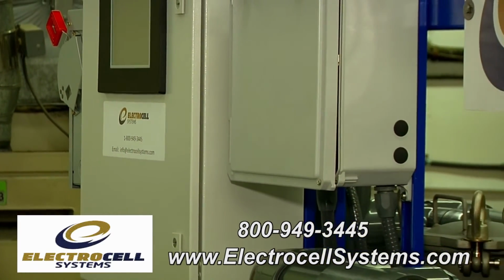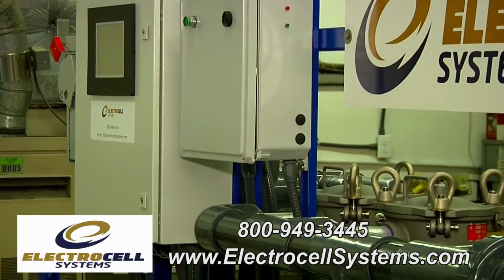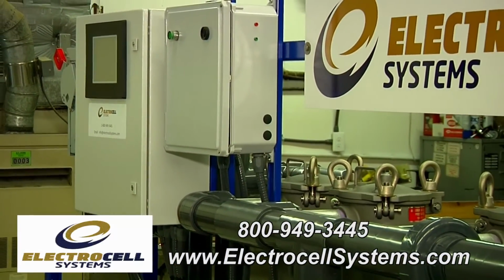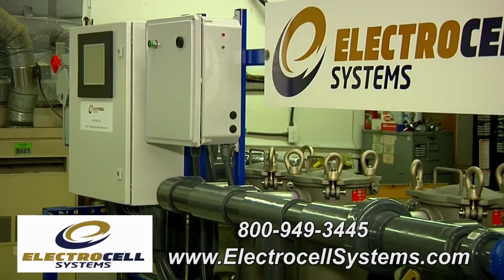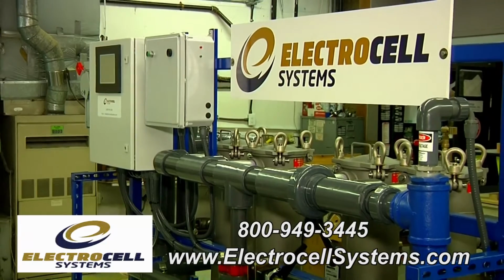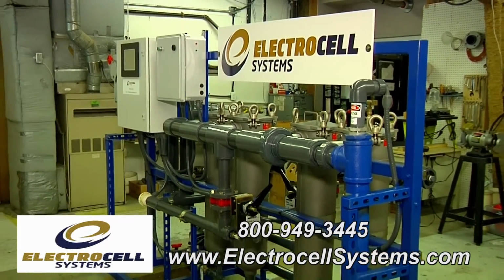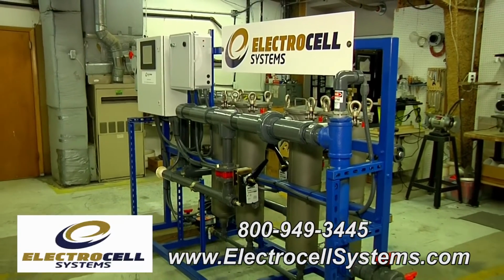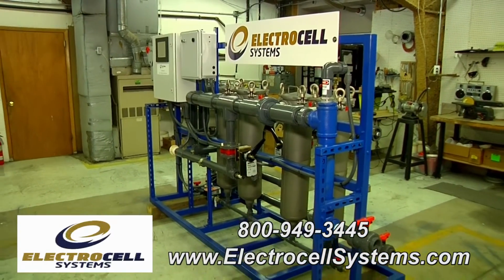We've been averaging close to 20 to 25% savings on water to the makeup in the tower, and we've been averaging 10 to 20% energy savings on the chiller, and that's across the board. Typically we would put in a 500 ton and up system. However, we do make systems that'll do under 500 tons. They are obviously a much smaller scale than this.